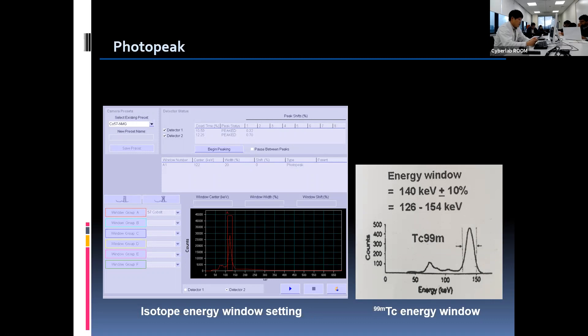High-voltage fluctuation can move the photopeak a few keV, so we should not forget to check the photopeak before we start any acquisition.